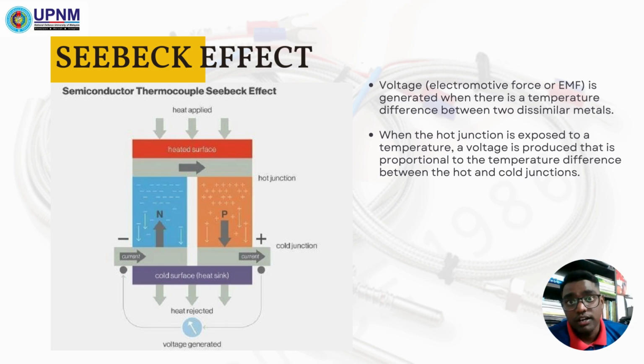As one of my colleagues said, we chose thermocouple type K. There's the Seebeck effect in thermocouple type K. So what is the Seebeck effect? Voltage, or electromotive force, EMF, is generated when there's a temperature difference between two dissimilar metals. When the hot junction is exposed to a temperature, a voltage is produced that is proportional to the temperature difference between the hot and cold junctions. As we can see in the picture, there is a hot and then a cold junction, and between them there's a temperature difference. This we call the Seebeck effect.